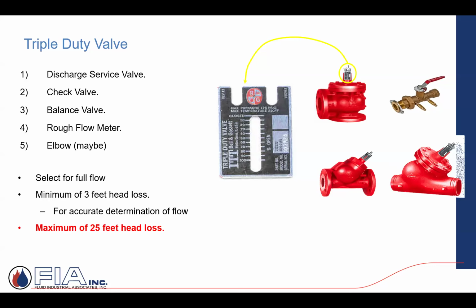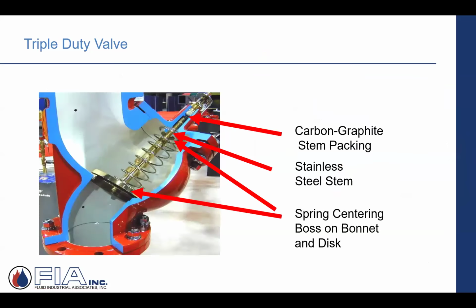So you've got the pump, you've got the suction diffuser, and on the discharge side, we're going to have this triple duty valve. And that's just a cutaway of what it looks like on the inside with that spring-loaded, soft-seated check.